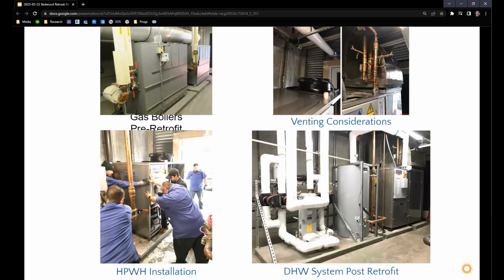Getting these big units into San Francisco was a fun project where we had to keep the boilers online. That's always a trick with existing multifamily properties, since people continue to need heat and hot water while you're building the plant. We had to take the boilers out one at a time and make our cutover within the same day, so there was never a loss of domestic hot water, and we were able to do that.